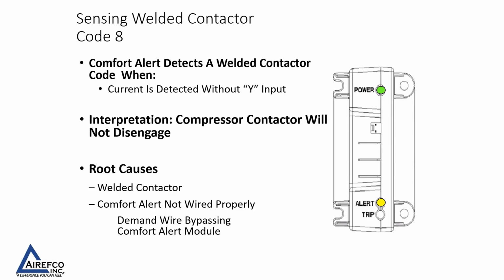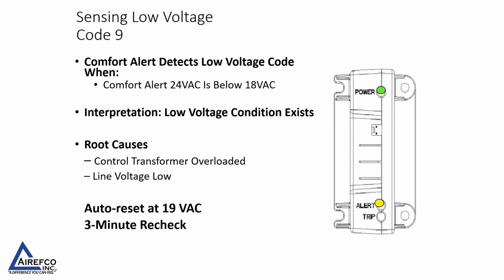So 8 flashes on the amber LED will tell us that there is a welded contactor, that there is no Y input, and yet we still have current being detected. So the compressor contactor is not disengaging. So we probably have a welded contactor, or the Comfort Alert is not wired correctly. If the amber LED is flashing 9 times, this means that it is sensing low voltage. The Comfort Alert detects low voltage when the 24 volts being supplied to it is below 18 volts. Could be a transformer overload, or it could be line voltage is dropping. This will auto reset at 19 volts AC and will recheck it every 3 minutes.